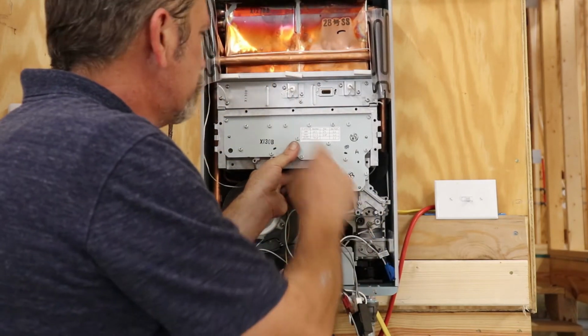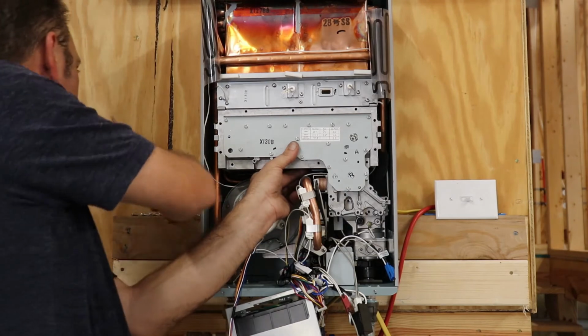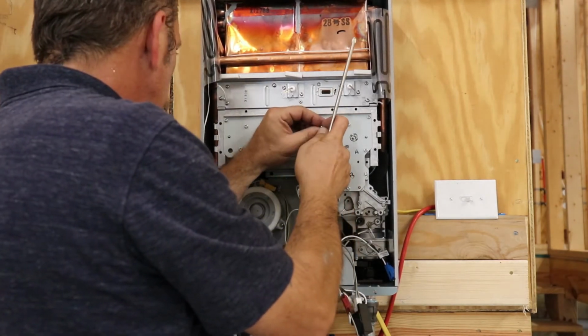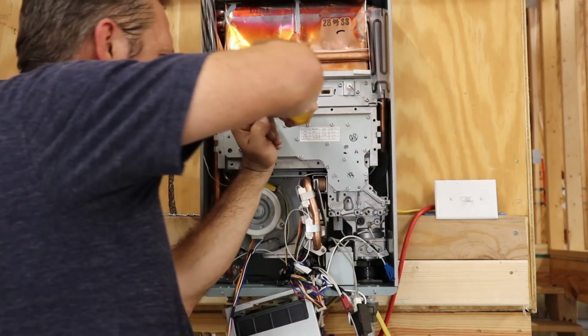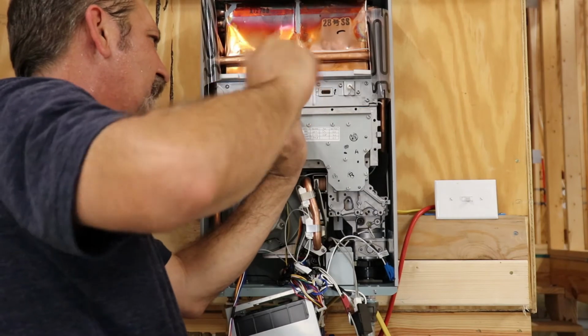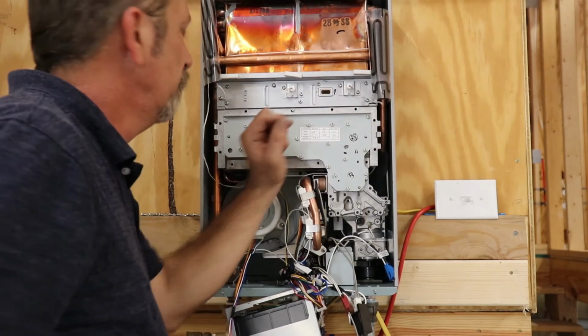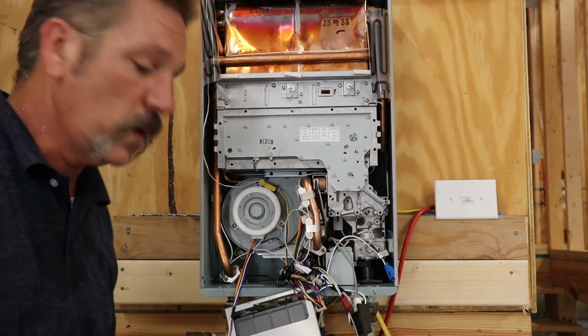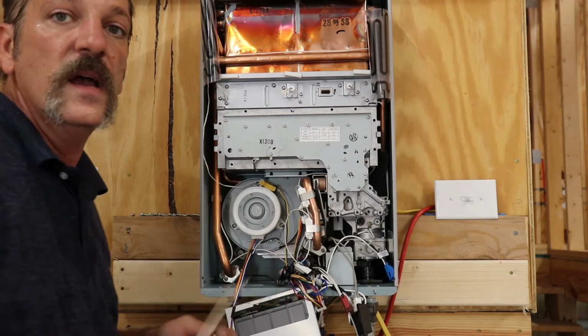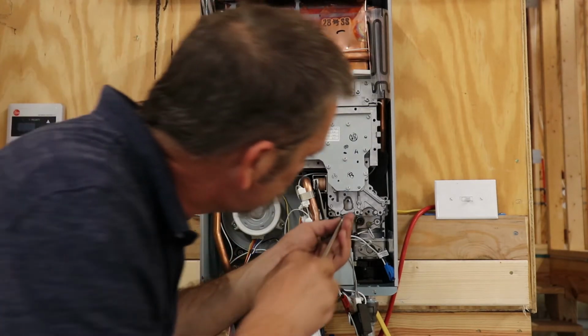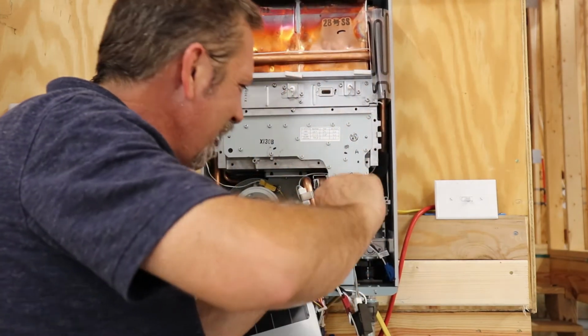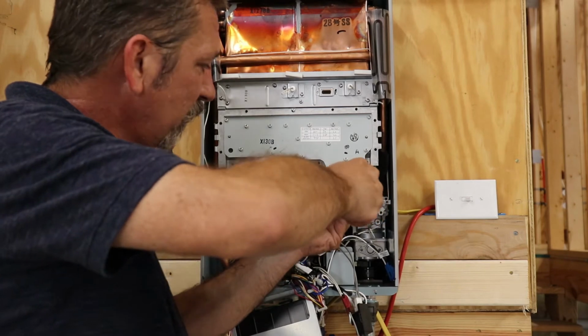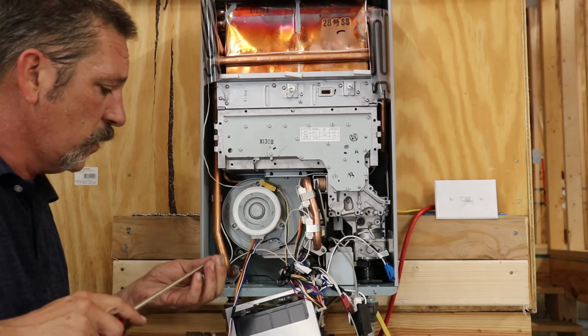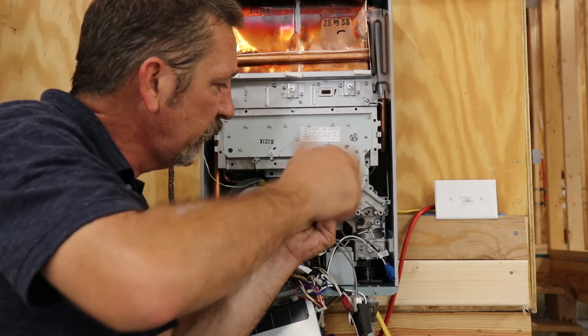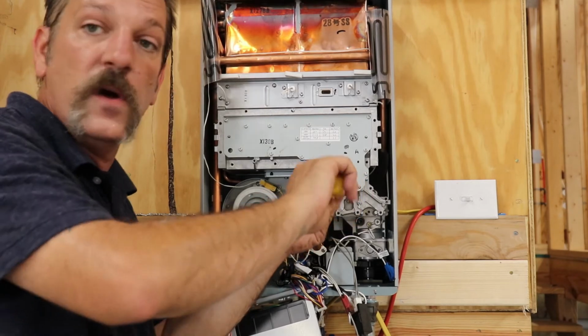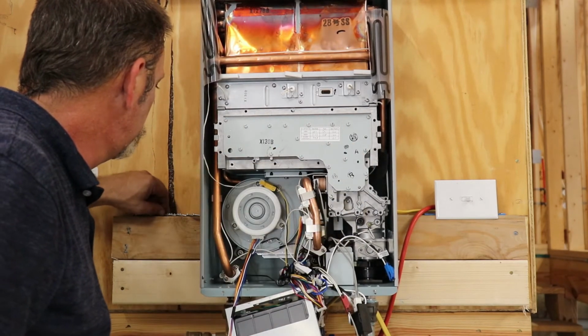With this, you're going to want to start at the bottom. Remember, don't get them too tight. Don't tighten down one side and think you're going to tighten the other. You just want to get them in there, and then do it like you change a tire—one here, one there, one here, one there, bringing it all down together. Because remember, this is aluminum, and you can strip out that housing. You do not want to do that, especially if you show up to somebody's house just to do a service, to clean a heater out, and now you've destroyed their water heater and you're trying to talk them into buying a new one.